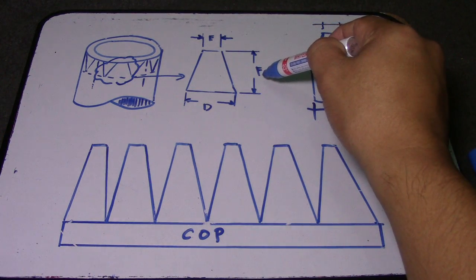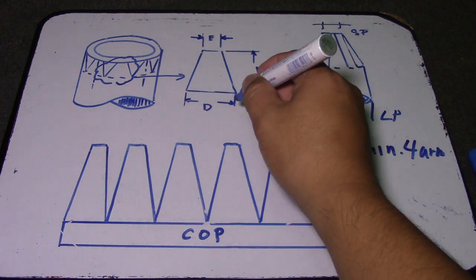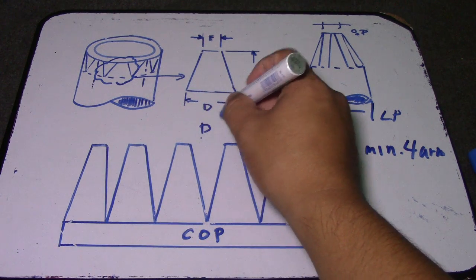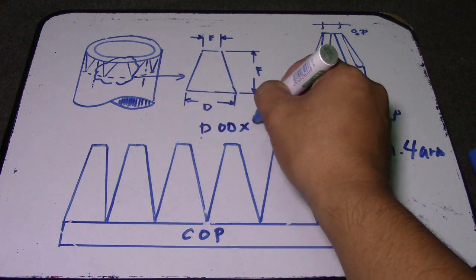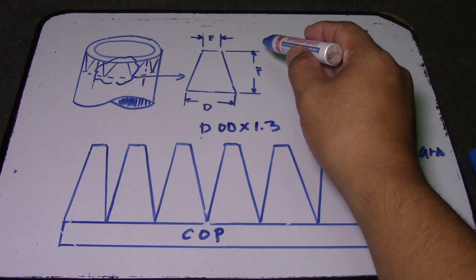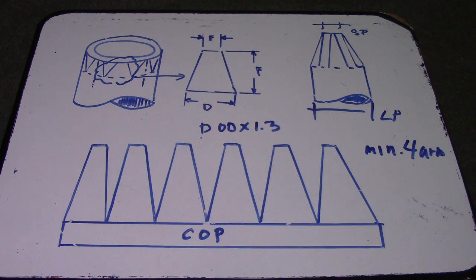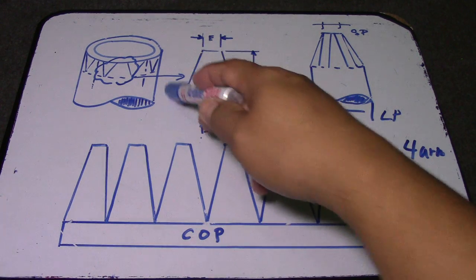Now we have letter F. To get letter F: difference of the pipe outside diameter (OD) multiplied by 1.33. That is the minimum. So difference of outside diameter multiplied by 1.33 gives you letter F. This is the full computation to get the layout from this pipe.